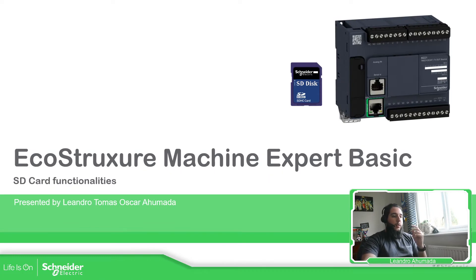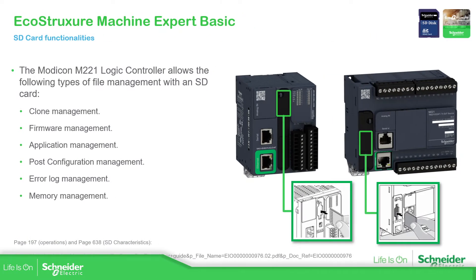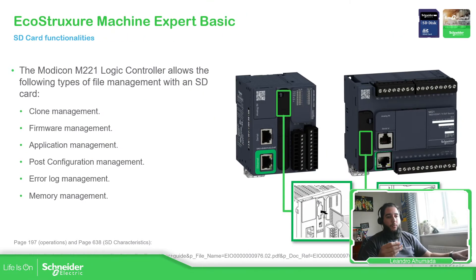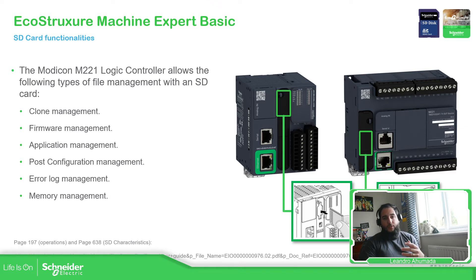With the SD card there are some functionalities we can do with our controller. We can clone the actual application on the controller and put it on the SD card. We also have the possibility to use the firmware update — we can download the firmware from the laptop to the SD card and then download it to the PLC. We can also download the application from the software to the SD card and then to the target. We also have the post configuration, which covers settings for communication ports such as Ethernet or Modbus serial — we can pre-define that, put it on the SD card, and then download it to the target.